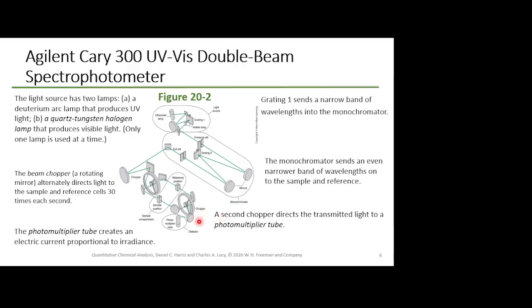Okay, so this right here is your detector portion. This is called a photomultiplier tube. It's essentially to take a relatively small signal and then we boost it up. This does cause some degree of error in your system, but it's a lot less error than just using more and more and more light source because these slits are narrowing down our amount of light source.